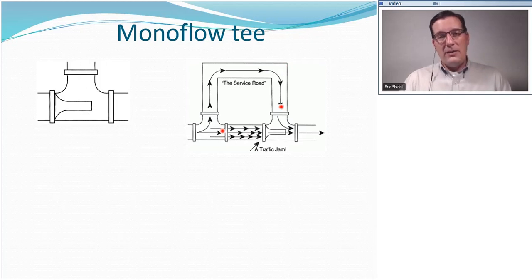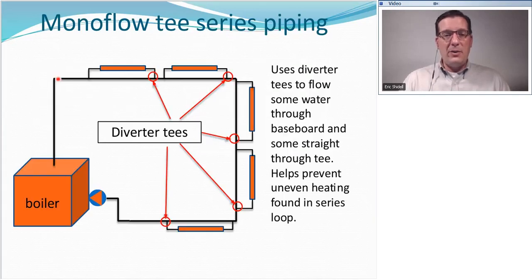Now, this helps alleviate some of the challenges that we had with the series loop piping, because as the water is going around, say we've got 180 degree water coming out of here, and some of that 180 degree water comes into here, and it comes back obviously cooler because it's given up some of its heat through the emitter, but it rejoins this 180 degree water stream, so the resulting water temperature falls, but not quite as much as it falls in the series loop system. This allows the emitter to be most effective, and it also reduces that around-the-way temperature drop problem. It doesn't eliminate it, but it alleviates it somewhat. And so this kind of gives us a good compromise between economy of piping and effectiveness of heating.